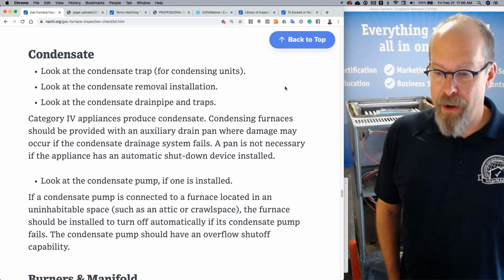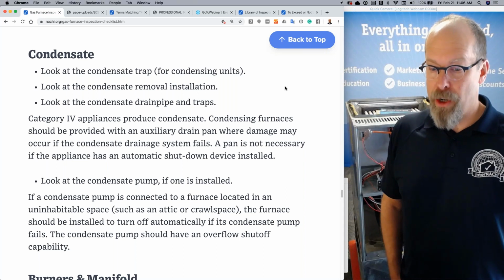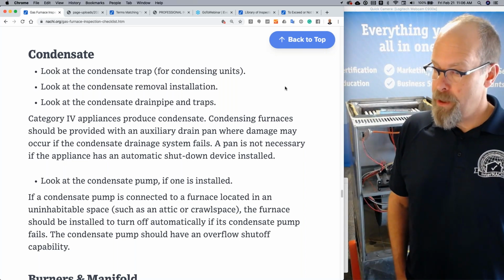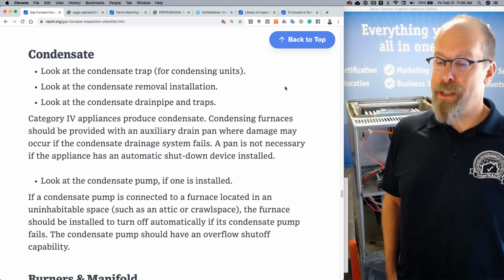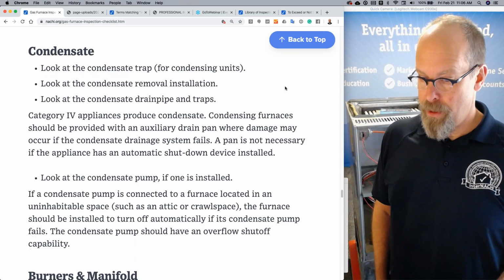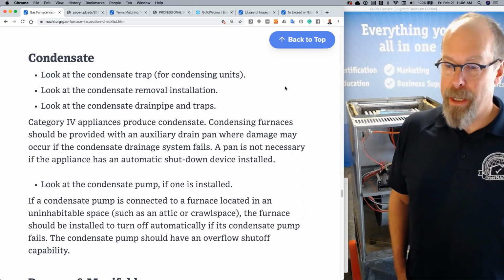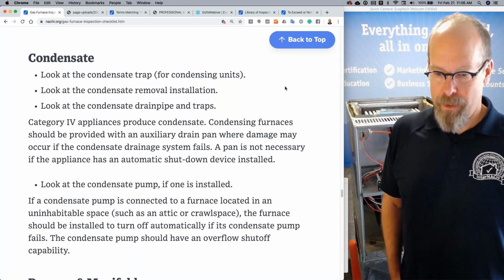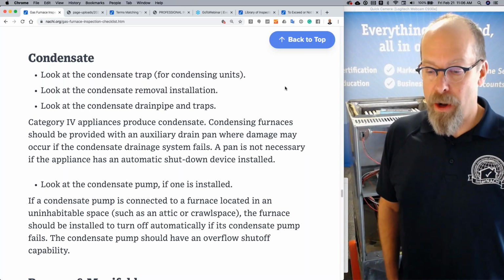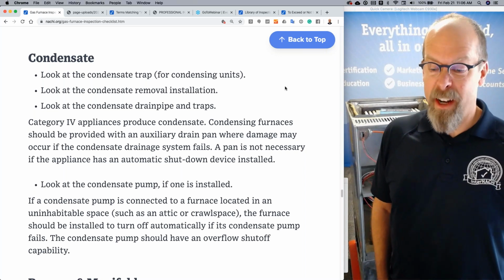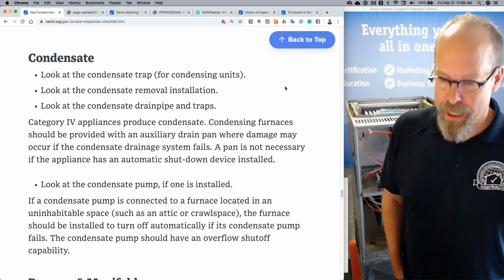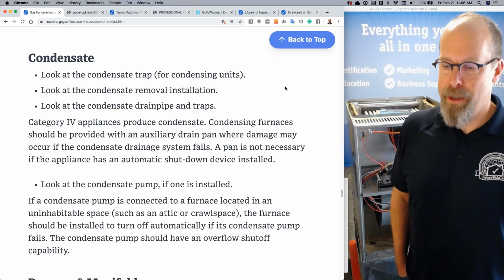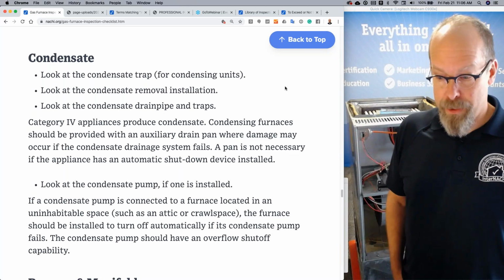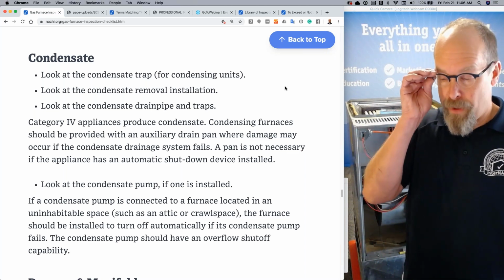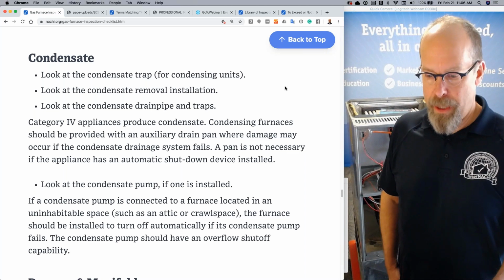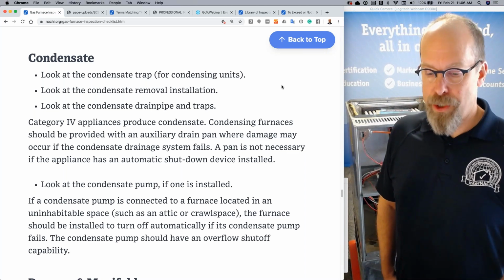Condensing furnaces should be provided with an auxiliary pan where damage may occur if the condensate drainage system fails. A pan is not necessary if the appliance has an automatic shutdown device installed. So I find those commonly in the attic spaces. Look at the condensate pump if one's installed. A condensate pump is connected to a furnace located in an uninhabitable space, such as an attic or crawl space. The furnace should be installed to turn off automatically if the pump fails. And the condensate pump should have an overflow shutoff capability.